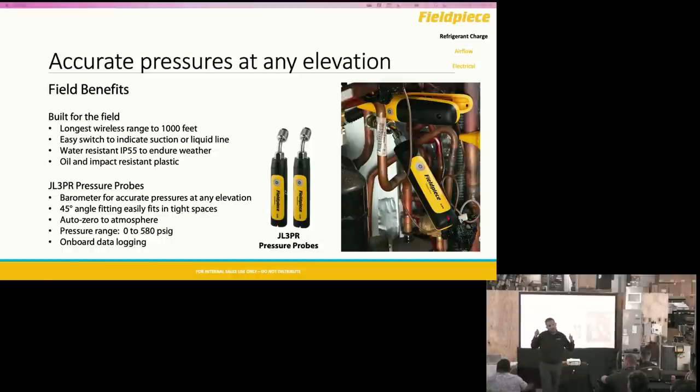The JobLink probes are the only ones with a built-in barometer to give you accurate pressure readings at varying elevations — every time you turn it on, it auto-zeroes to whatever elevation you're at. A common question: can I charge with refrigerant using a pressure probe? Yes — use an XST valve core removal tool. I get that question so much I created a two-minute how-to video on Fieldpiece University on how to actually do that. It's not difficult. Myth busted.